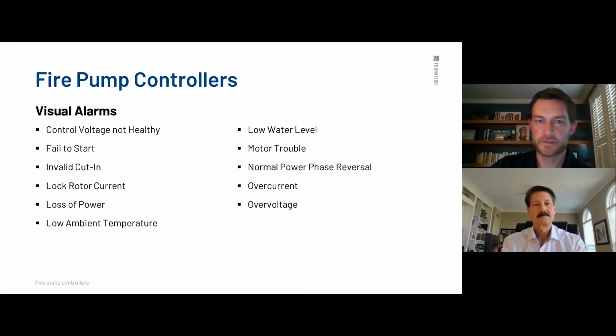Control voltage not healthy, fail to start, invalid cut-in. All of these are going to be alarms that pop up on the screen and go into the alarm section. Overcurrent, under voltage. All of the data that you see on the ViZiTouch is the true RMS value. So when the voltage readings in our demos and these pictures show a very healthy 480 volts, obviously the real voltage is going to fluctuate a bit, and you're going to see those numbers going up and down. Same thing with the motor amperages. And overcurrent, under voltage, those types of things, they're watching all of that data, and anytime there's an issue, it's going to pop up with an alarm on the screen.